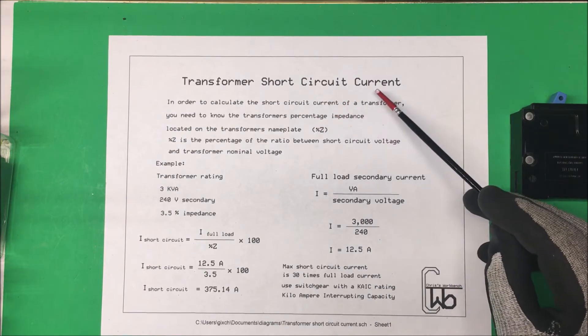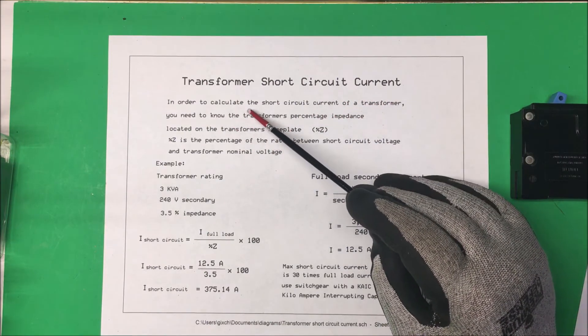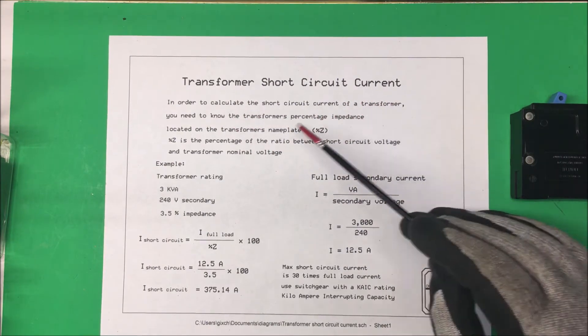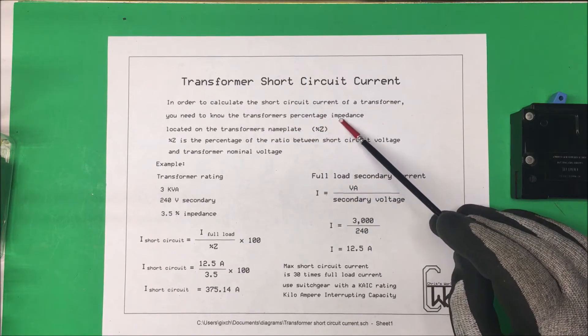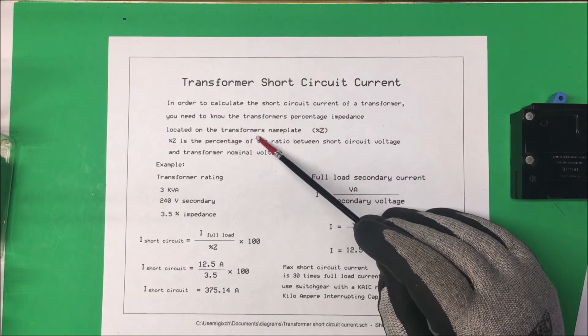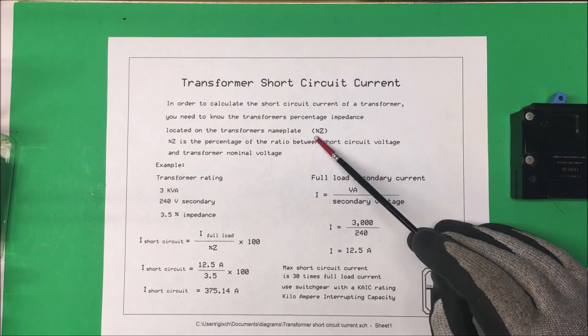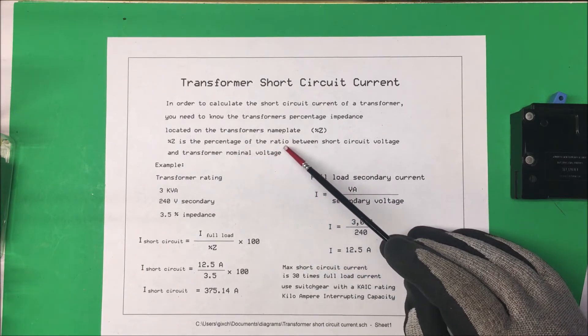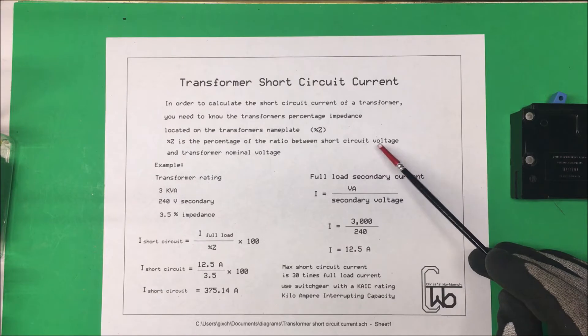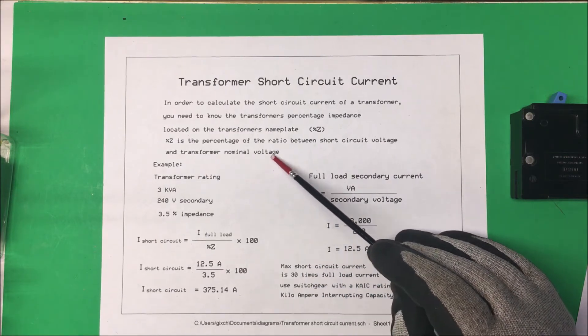Let's take a look at a transformer short circuit current. In order to calculate the short circuit current of a transformer, you need to know the transformer's percentage impedance, and that's usually located on the transformer's nameplate under percent Z. The percent Z is a percentage of the ratio between a short circuit voltage and the transformer's nominal voltage.